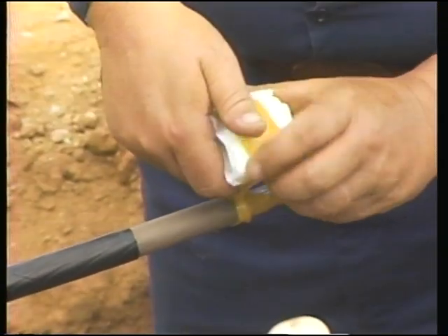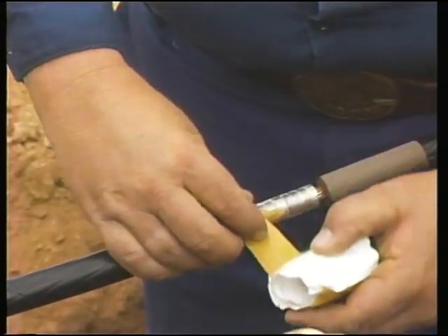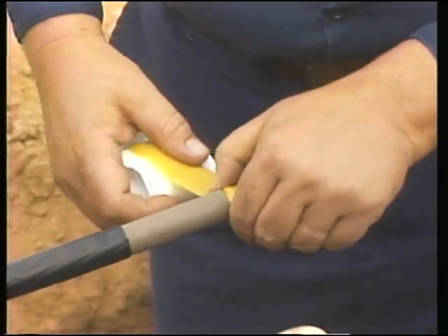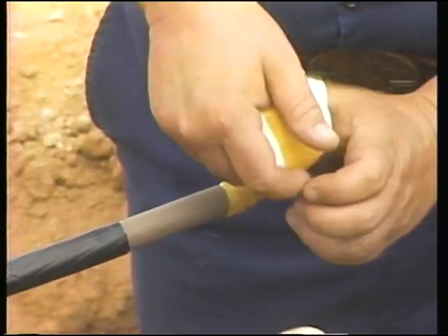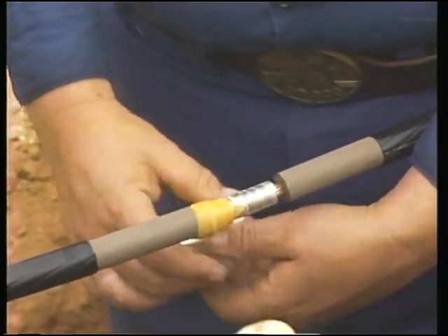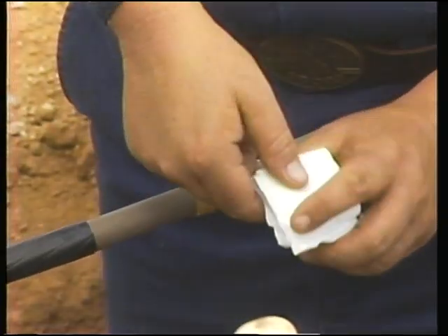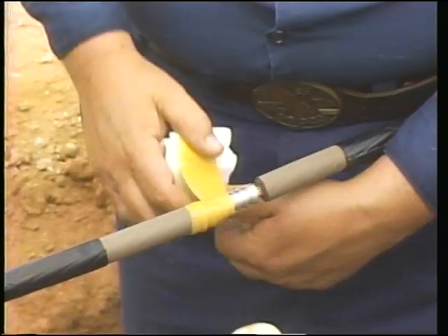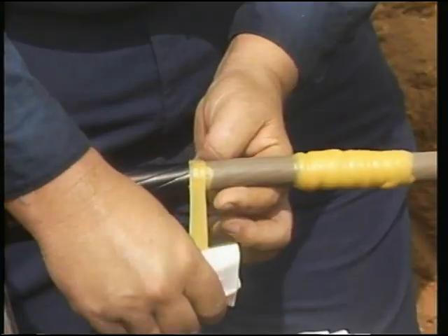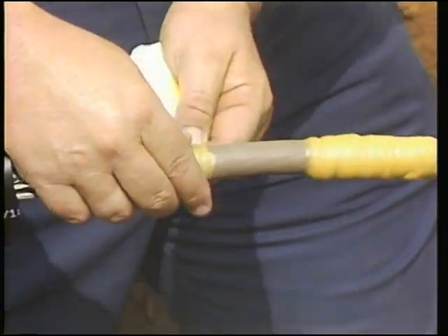After cleaning the splice area, stress control putty is applied to the cable's conductor and then along the edges of the semiconductor layer. The putty placed on the conductor splice is applied to the same thickness of the cable insulation, along with the first of the 3 heat shrink tubes. The putty provides the voltage stress handling properties of the original cable.